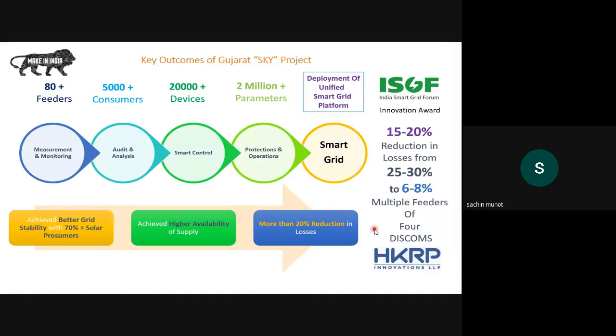This has been recognized by the India Smart Grid Forum and rewarded with an award for this project. We achieved 15 to 20% reduction in losses, from 25 to 30% existing losses down to 6 to 8%, across multiple feeders of all four discoms of Gujarat. Out of 80 feeders, this loss reduction to 6 to 8% has been achieved on almost all of them. That was the key outcome of the Surya Gujarat project, the Surya Shakti Kisan Yojana project.